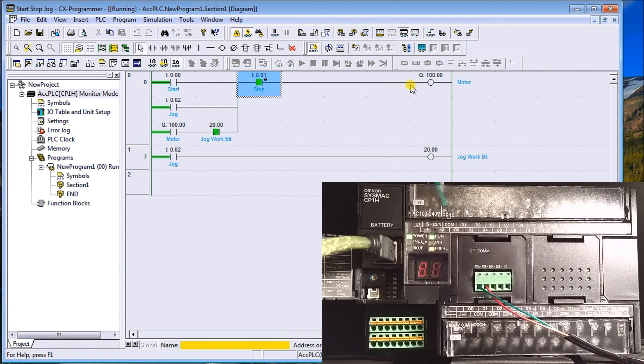To make the motor condition come on we'll also need to hit start. Forcing means that regardless of what the PLC scan is saying, we're going to keep that bit on — that's why we see the lock symbol. The other option is Set. Set will turn it on for one scan during that condition, and then the I/O will take over again.